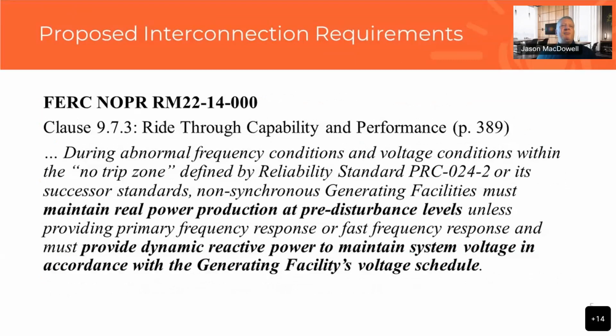So I wanted to also offer maybe a humble opportunity to give some feedback on an area where there's an opportunity for harmonization, and maybe give some feedback on some of the language in the FERC NOPR and the IEEE 2800 standards and the NERC standards. So one of the clauses I picked out here was from clause 9.7.3, the ride-through capability and performance. And this clause basically says that for a system disturbance, for abnormal frequency and voltage, the facility must maintain real power production at pre-disturbance levels unless providing PFR or FFR. It must provide dynamic reactive power support to maintain system voltage in accordance with the generating facility's voltage schedule.